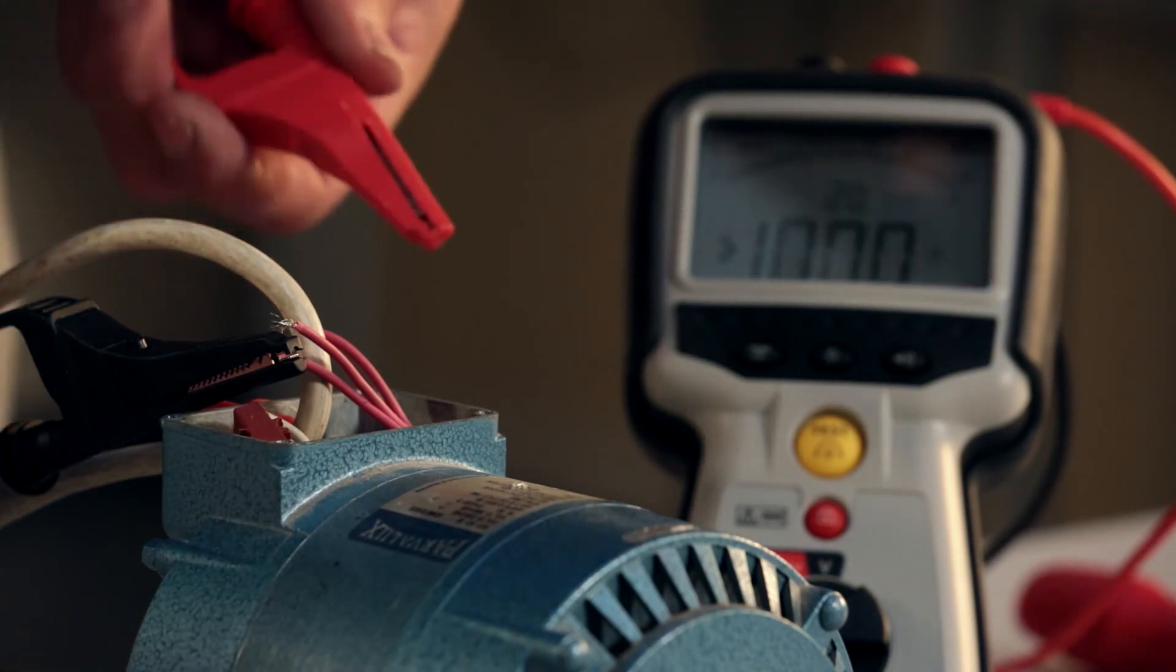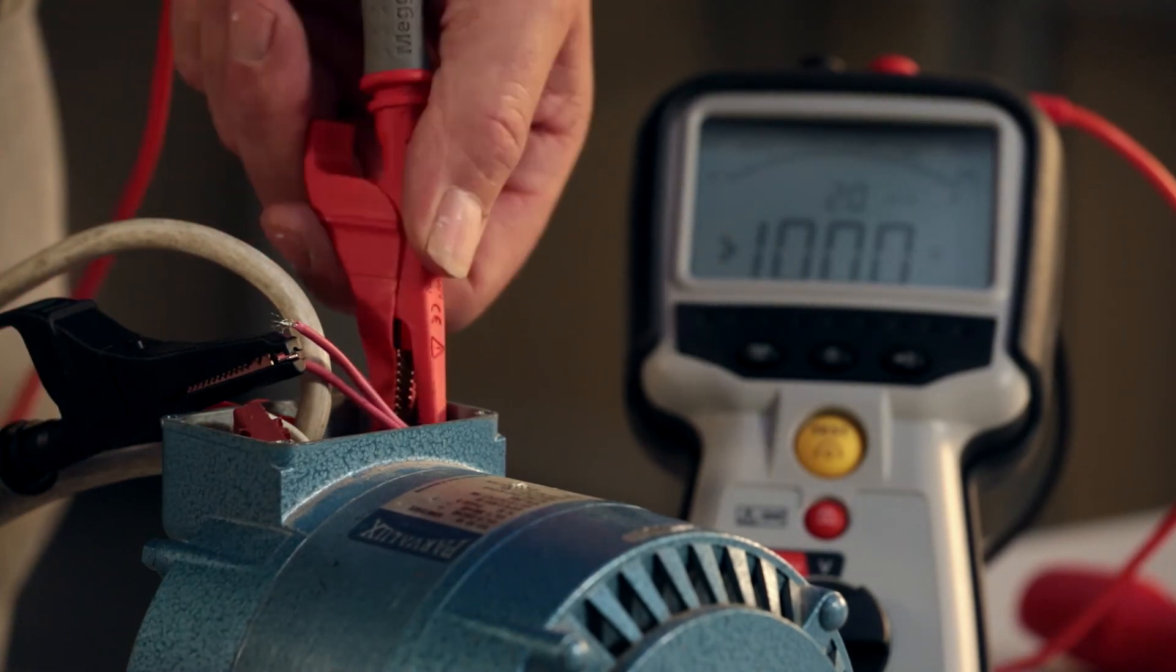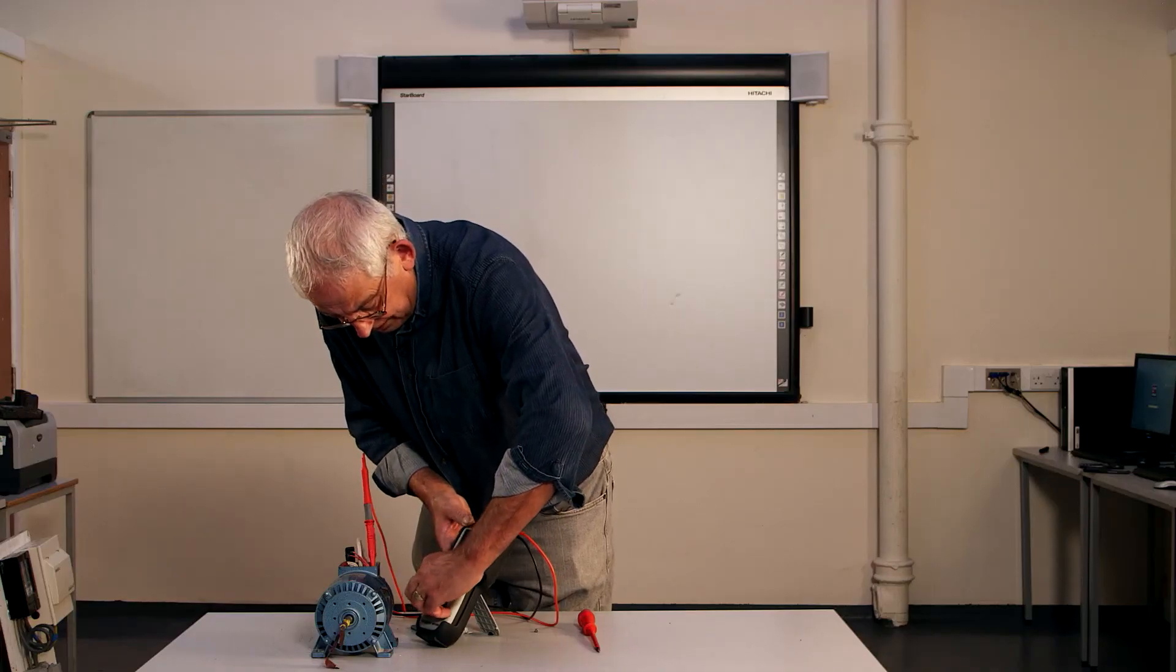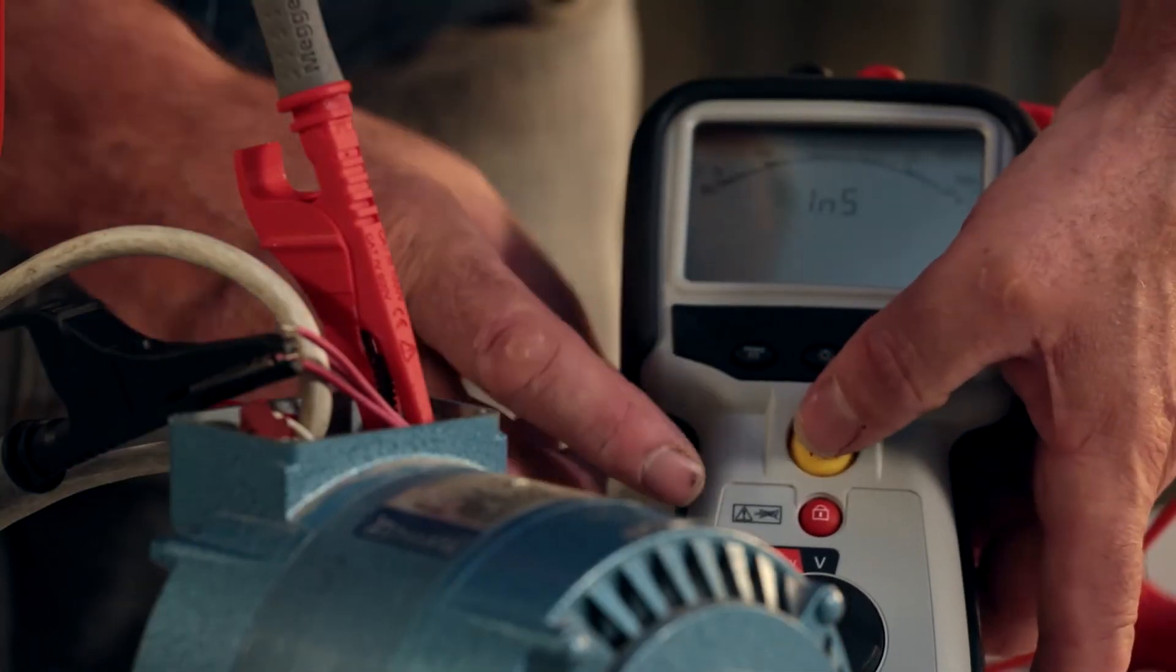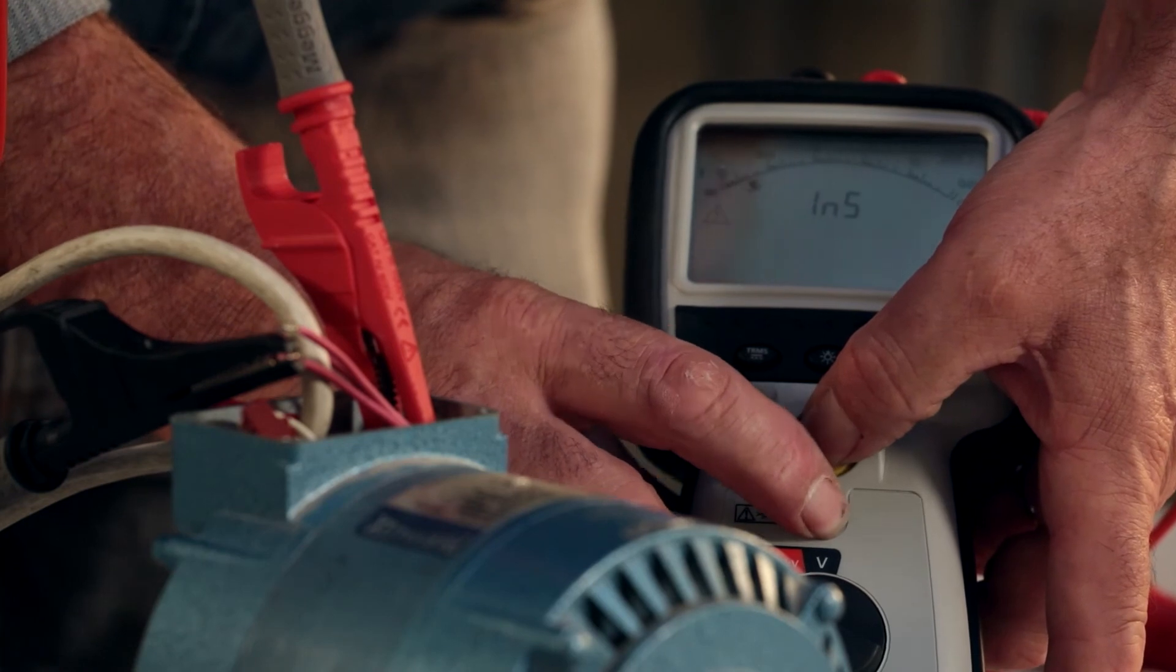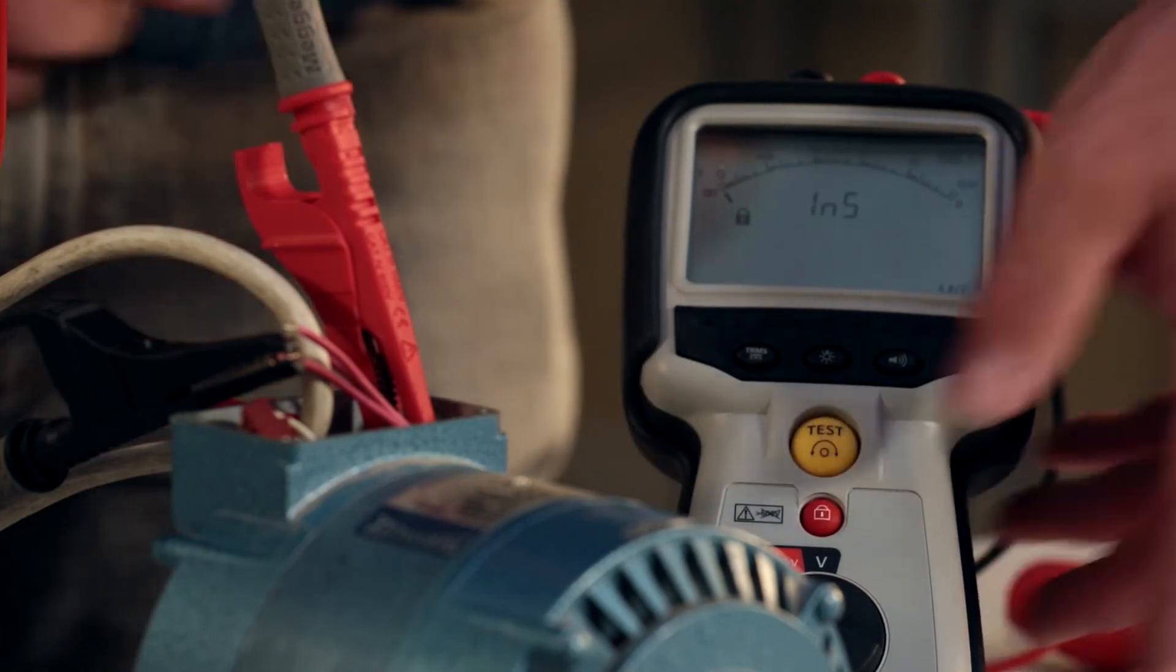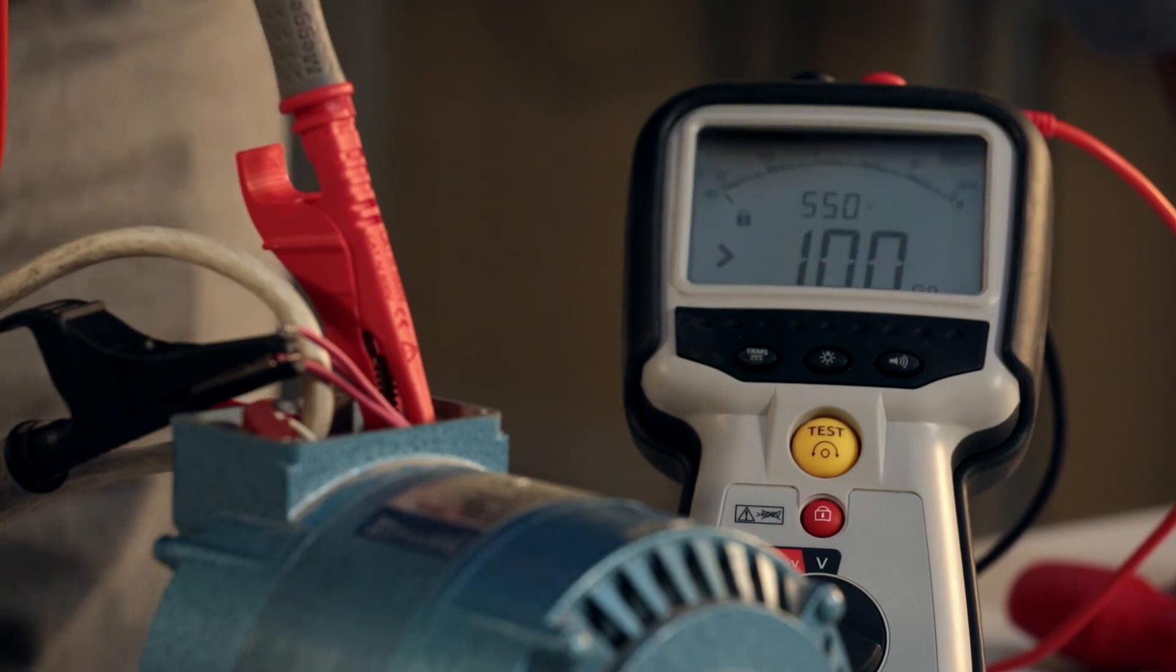I need to find a good earth. Inside here, I've got a nice clean connection, set this to 500 volts, push the button and lock it and just let it run for a minute or two and we'll see.